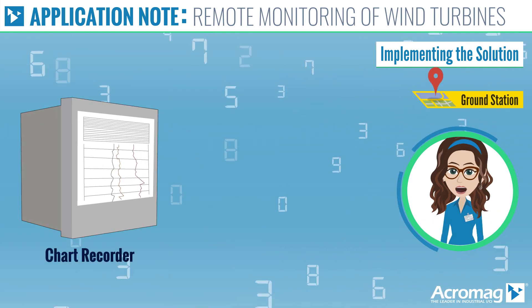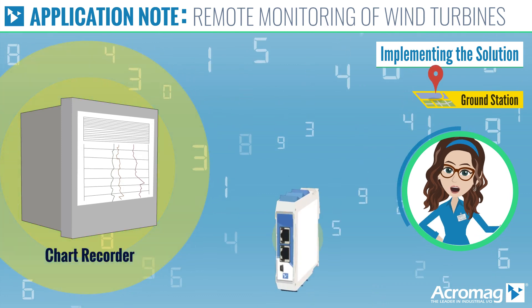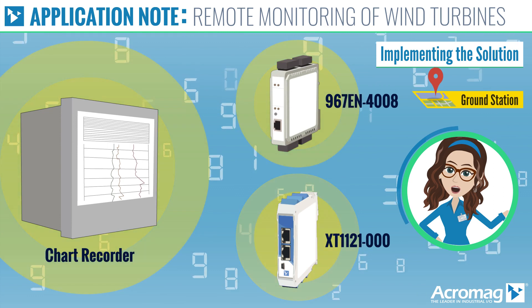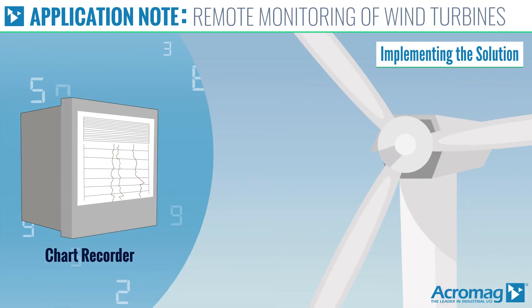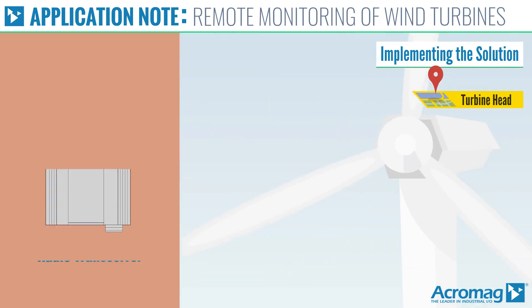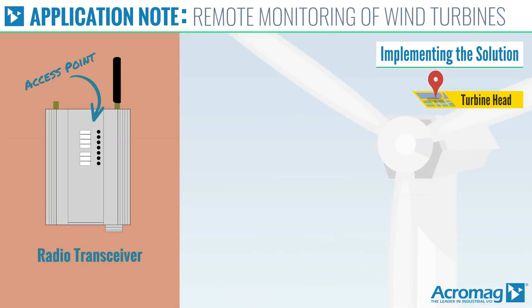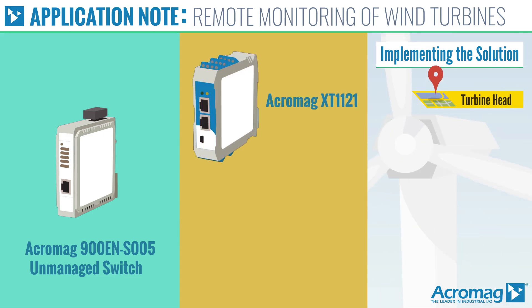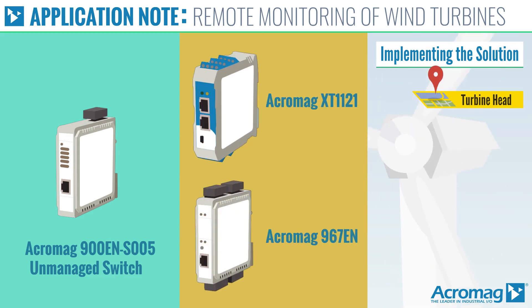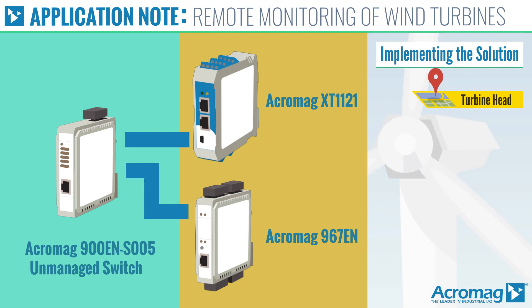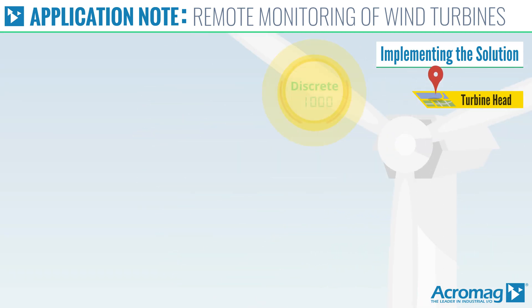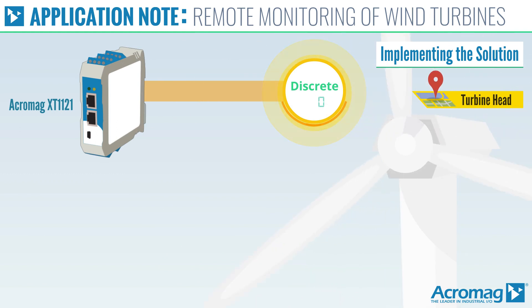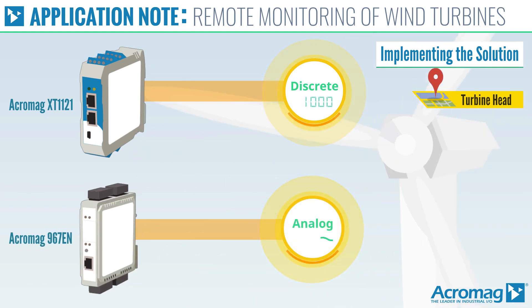Configure the chart recorder to communicate to the XT-1121 and 967-EN Acromag Modbus server modules. At the wind turbine head, configure the radio transceiver as an access point and connect the ethernet port to one of the ports on a 900-EN unmanaged switch. Connect the XT-1121 discrete I/O module and the 967-EN analog current input module to two of the other ports on the 900-EN switch. Finally, connect the discrete signals to the XT-1121 inputs and the analog current signals to the 967-EN inputs.